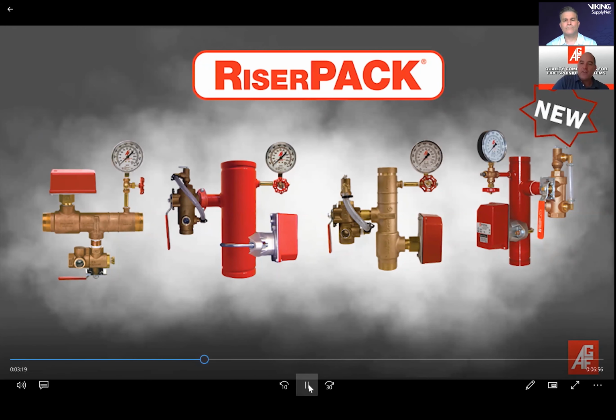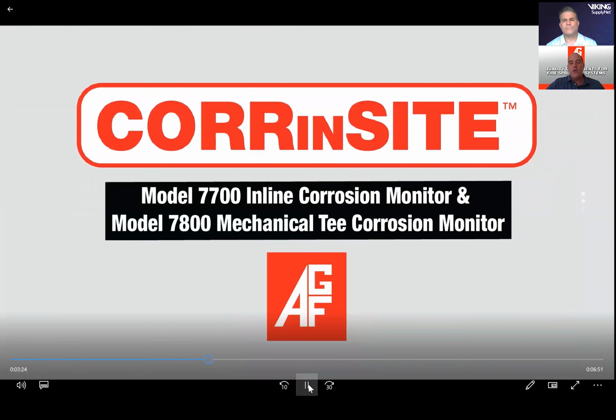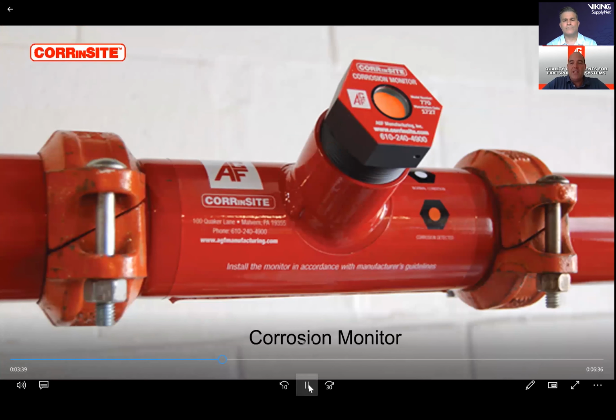And from the test and drains to the riser packs, we started to get into corrosion monitoring, corrosion detection. What causes corrosion? How do we tell there's corrosion? So we introduced the CorrInSite, and this is a simple sight glass you put onto a system that will change to bright orange if you have corrosion problems on the system. It's a hollow steel plug.